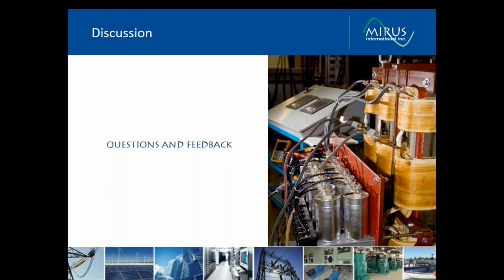I have a question regarding the first question I asked. Remember, it was about initializing the system, mitigating the harmonics prior to initializing the system. So they're asking, the system I've been dealing with has caused reverse current protection in this main switchboard to trip and caused the generator circuit breaker to trip. Is this caused by the voltage distortion? Maybe not. It could be harmonics or it could be high frequency, maybe not necessarily harmonics.